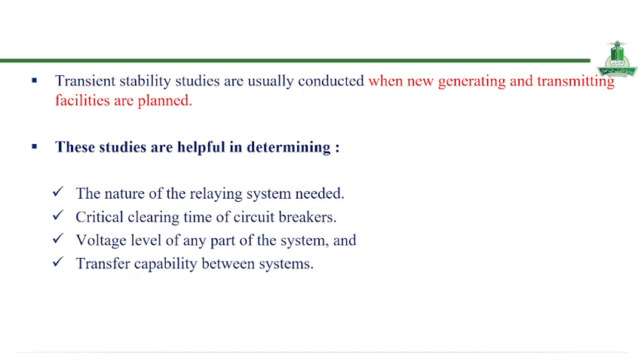I want to say that transient stability studies are typically carried out during the planning stage of new generating stations and transmission systems. These studies play an important role in ensuring that the power system will remain stable under severe and realistic disturbance conditions before the system is actually built or expanded. They are useful in determining several key design and operational requirements, including the type and settings of the protection relaying system needed to safeguard the network. They also help in identifying the critical clearing time of the circuit breakers, which is the maximum time allowed to clear a fault before the system becomes unstable.